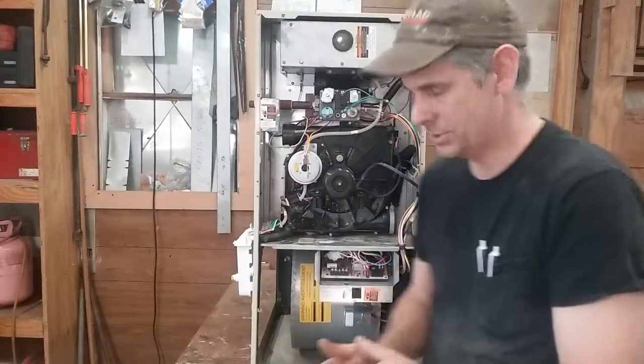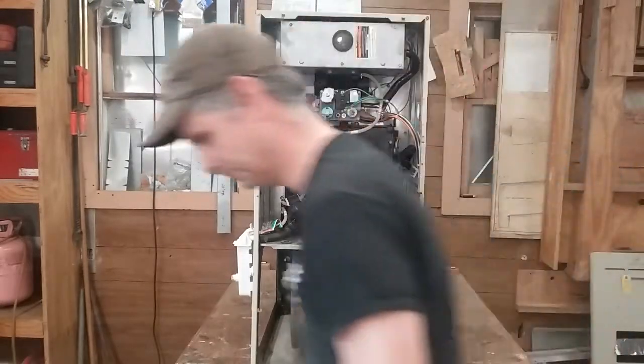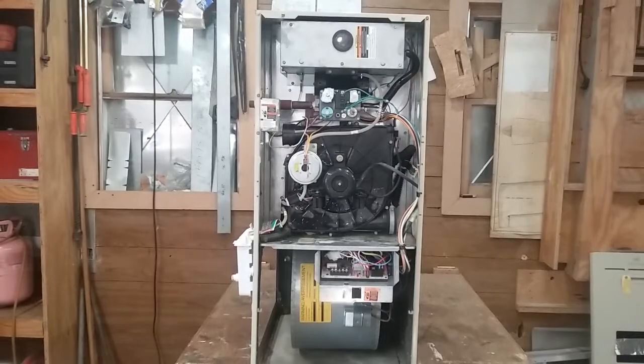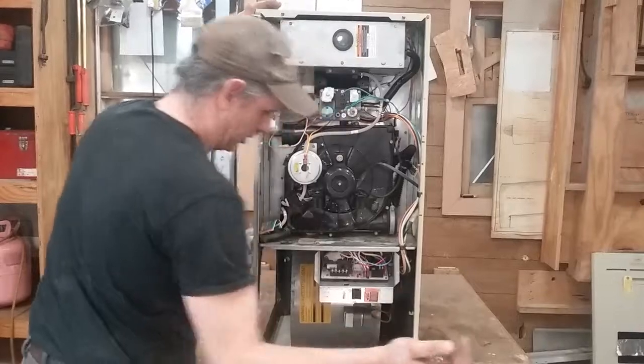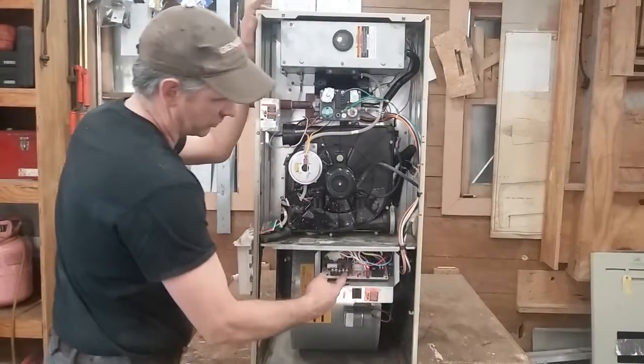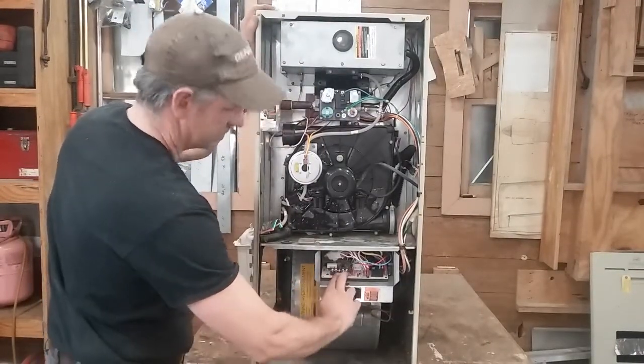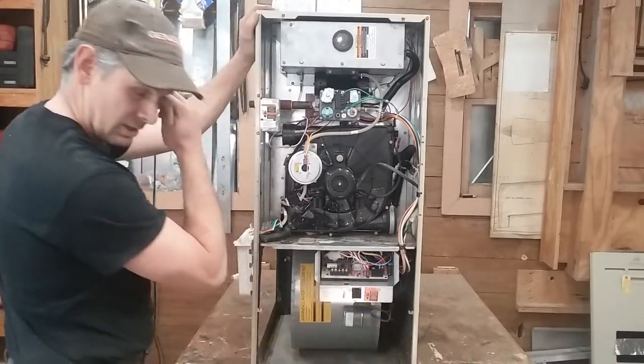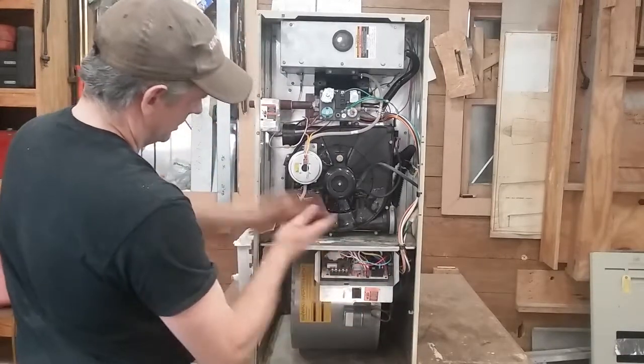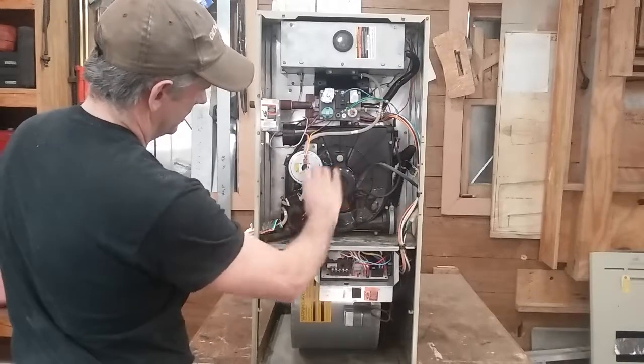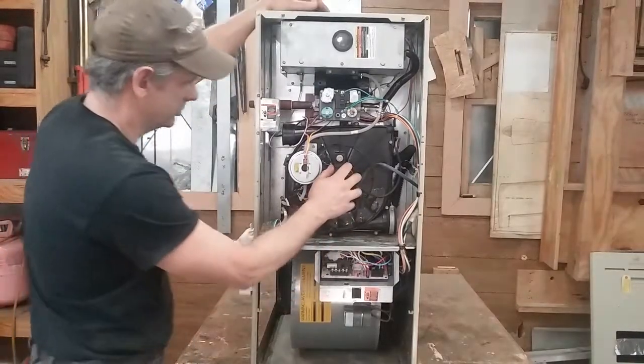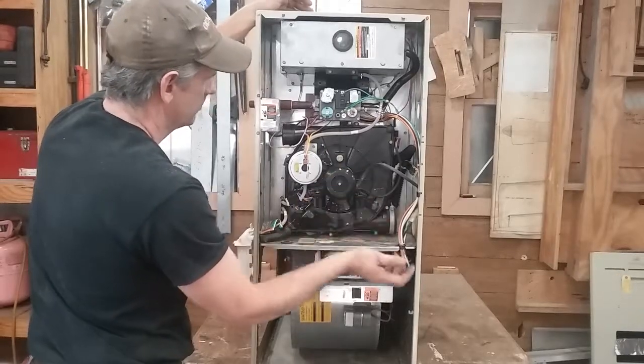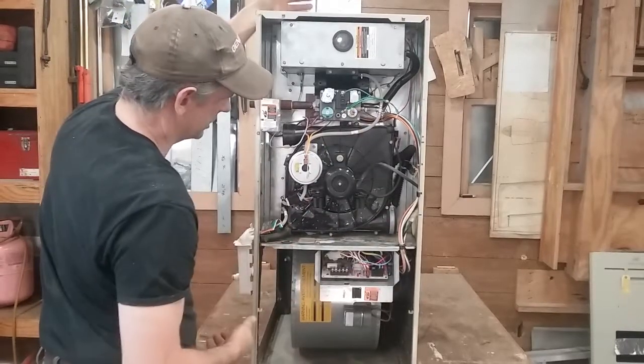So anyway, let's start off with the simple stuff. Just kind of a little sequence of operation on how a furnace works. So you get a W call at your thermostat. That means the thermostat took a 24-volt signal from red and tied it to W. And when you get a W call, the control board kicks in, and the control board turns on the induced draft blower. The induced draft blower comes on, pulls a vacuum through the heat exchanger.